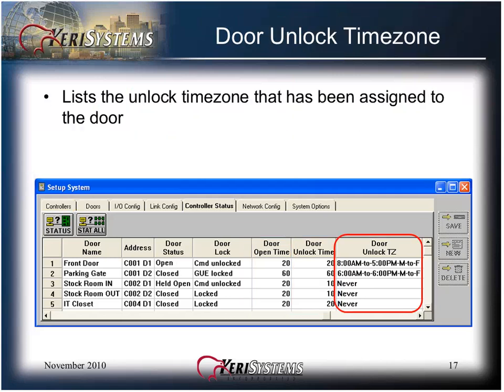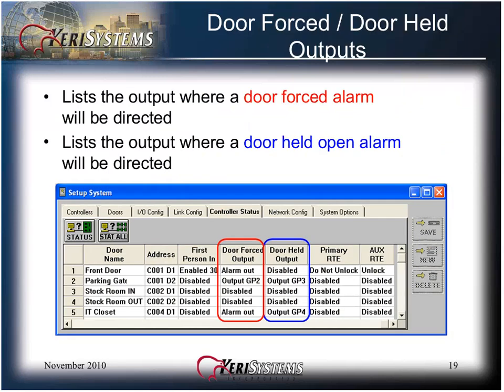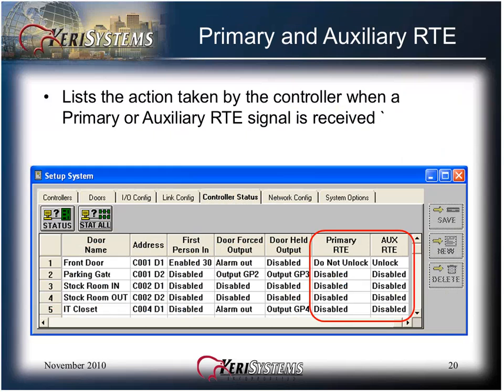This information cannot be edited in this window. The door unlock time zone lists the unlock time zone assigned to the door. The first person in column lists the value assigned to that door if first person in has been enabled. The door forced output and door held output columns list the output where a door forced alarm or a door held open alarm will be directed. The primary and auxiliary request to exit columns list the action taken by the controller when a primary or auxiliary request to exit signal is received. All of these values come from the setup system doors tab and cannot be edited here. To update values, go to the doors tab, change the values there, save them, then do another controller status to see the new values in this screen.